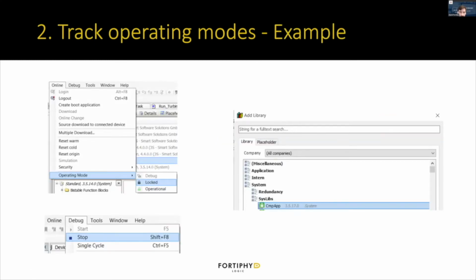For the example, looking at what CODESYS provides. So if you go into the online menu at the very top, you can see operating mode. There are 3 different modes: debug, locked, and operational. Debug is the default mode, just what you do all the programming in. Locked and operational, there are slight differences there, but they both just prevent changes to the program.